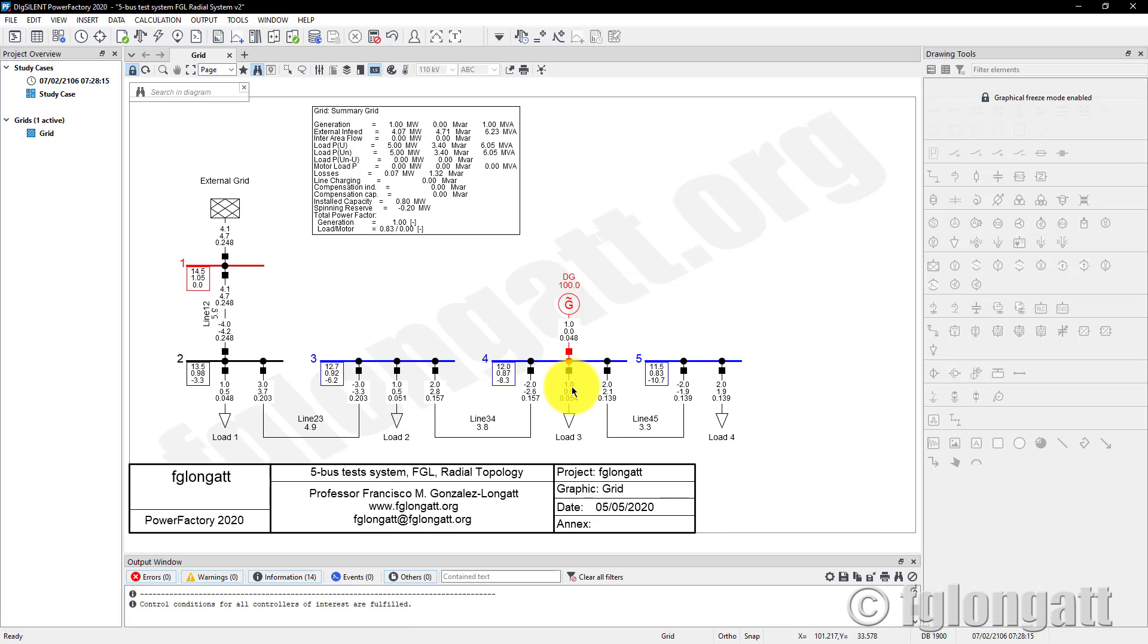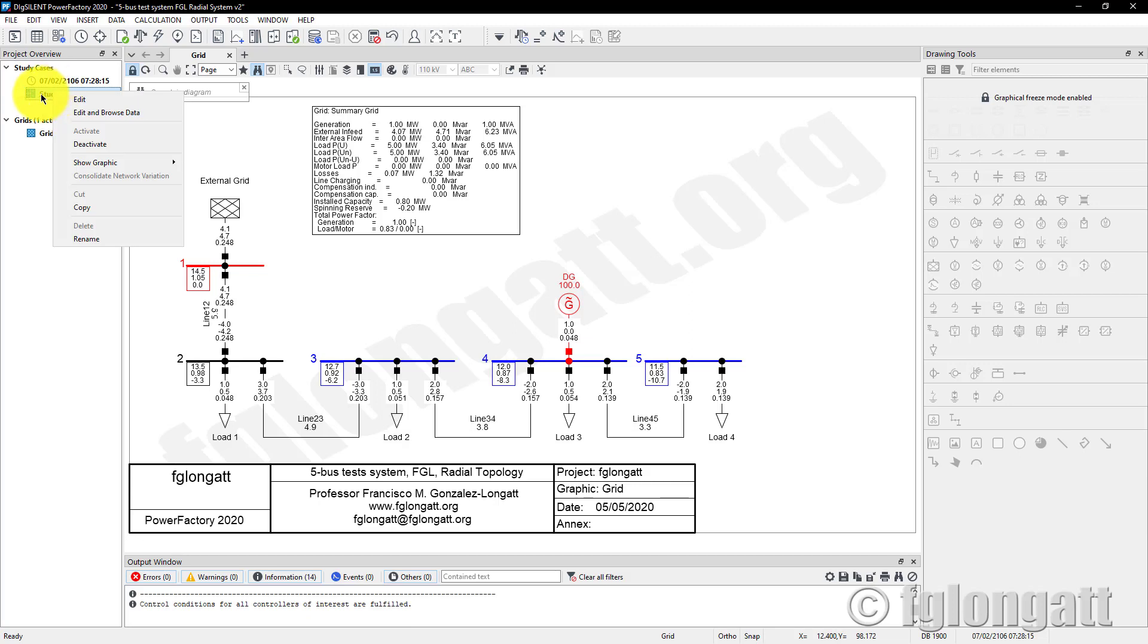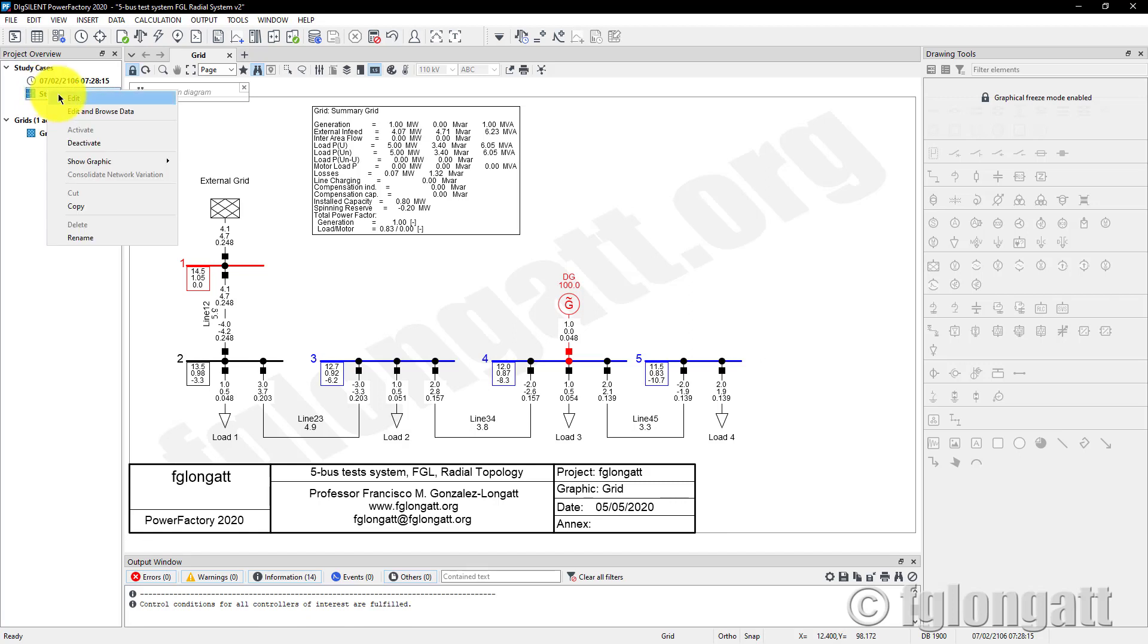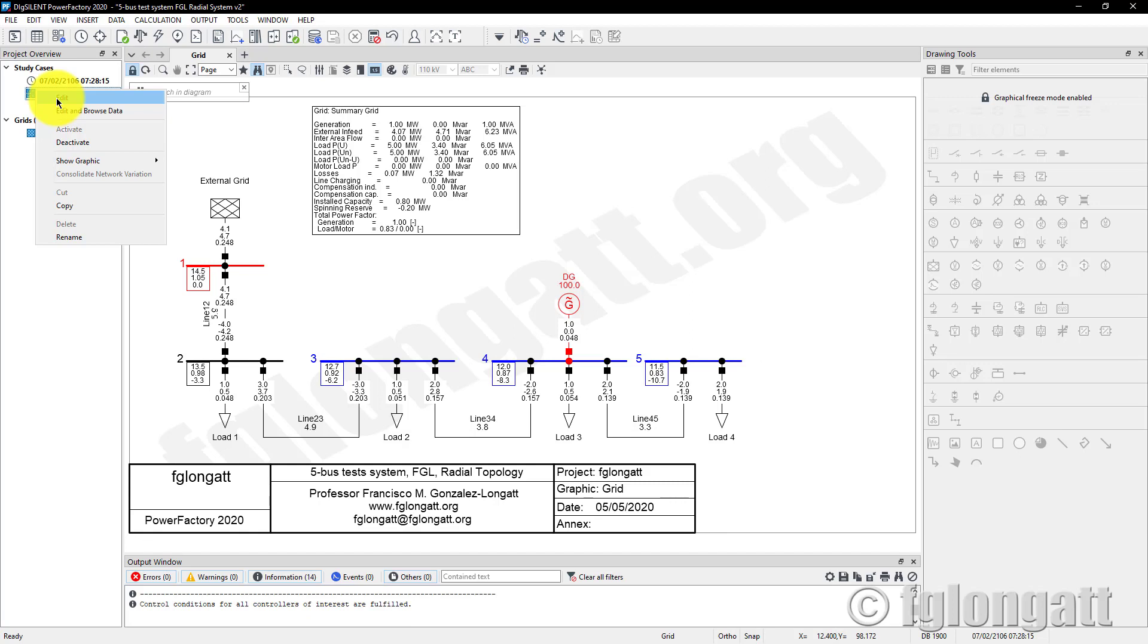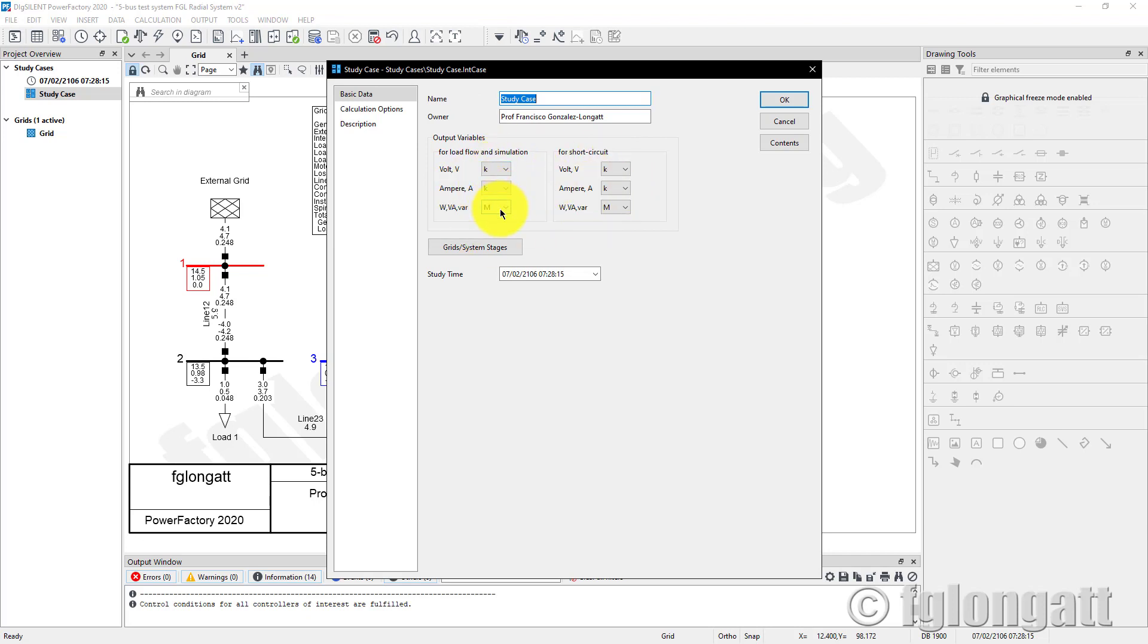The first thing I will show you is one way to change all the numerical results. If you go to the study case, right-click and select Edit, it's extremely simple. Here you have the output variables in the basic data, and you can change the representation for load flow to kilowatts, kVA, and kVAR.